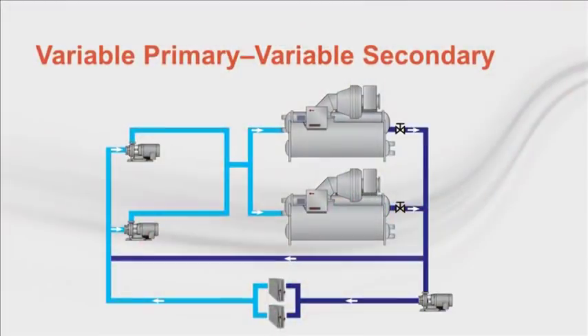For our example, we're going to start with primary pumps that are manifolded. First, the change involves adding a VSD to the primary pumps and opening the balancing portion of the triple duty valve wide open, using the VSD to balance the flow rate and set the maximum pump speed. You'll likely save energy just by doing that.